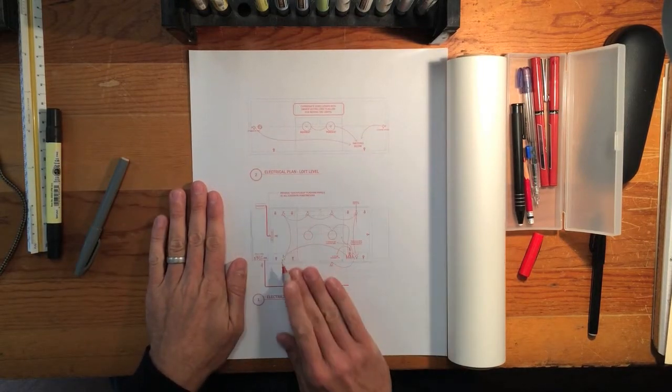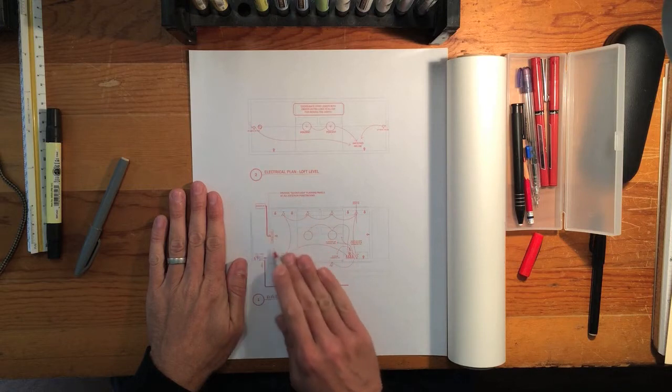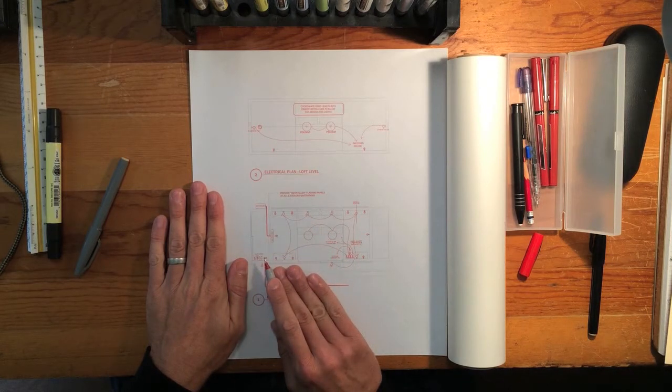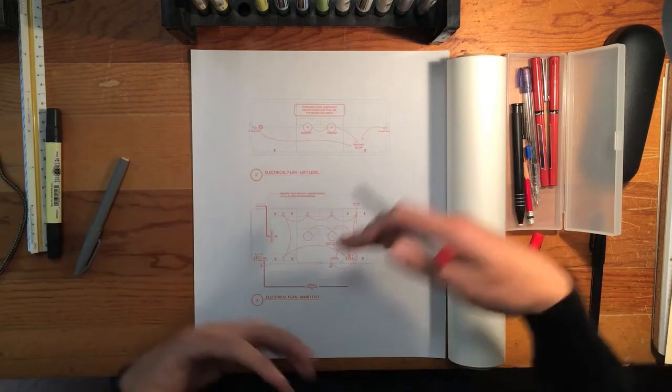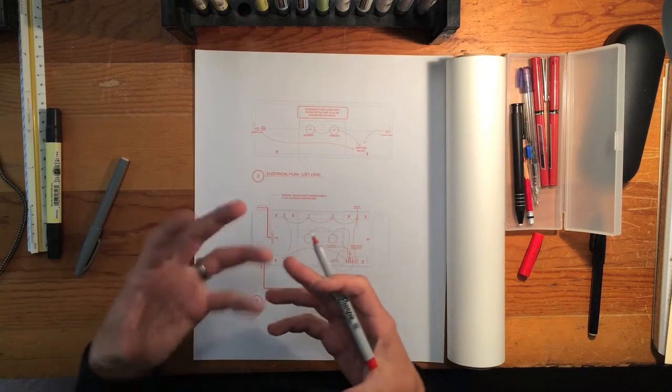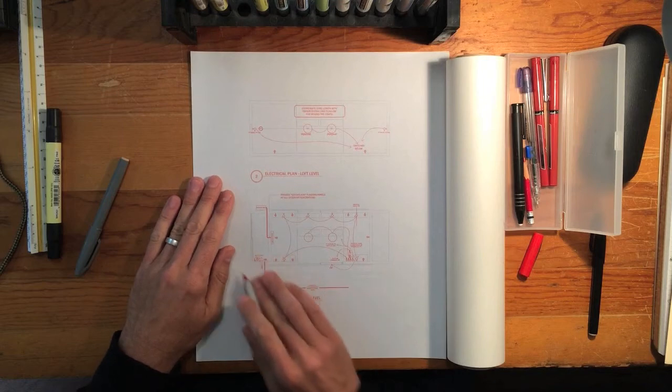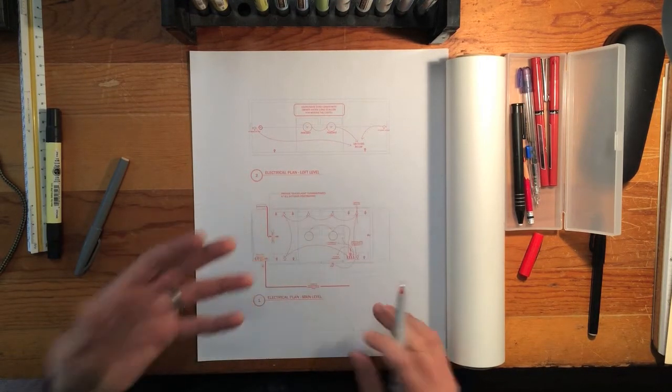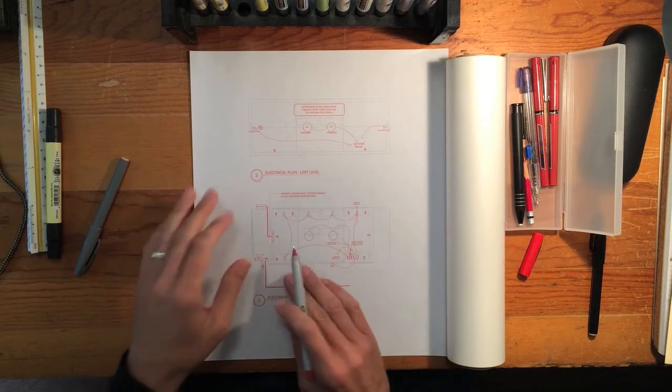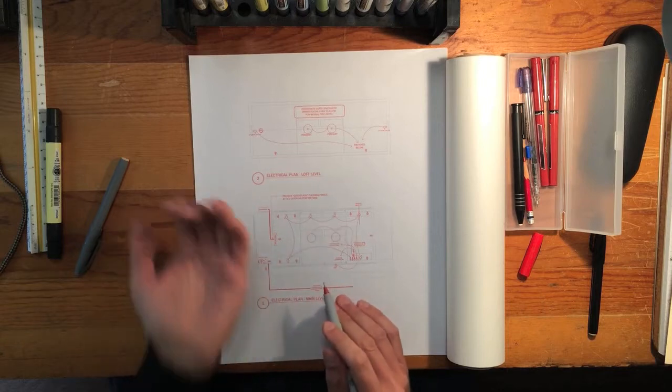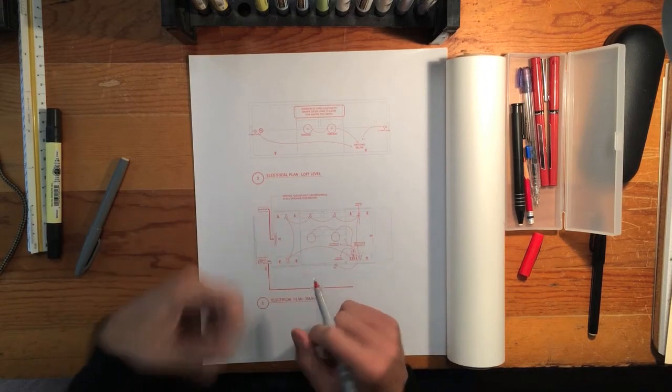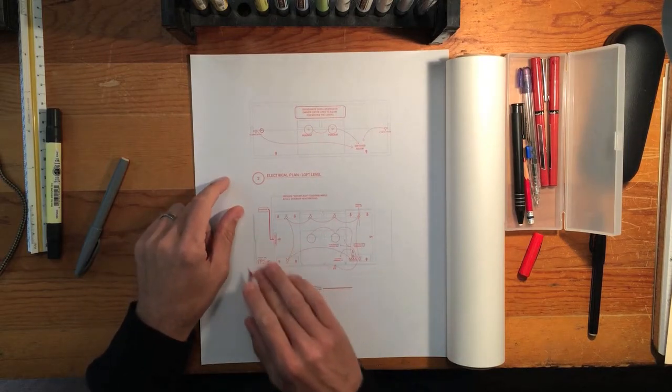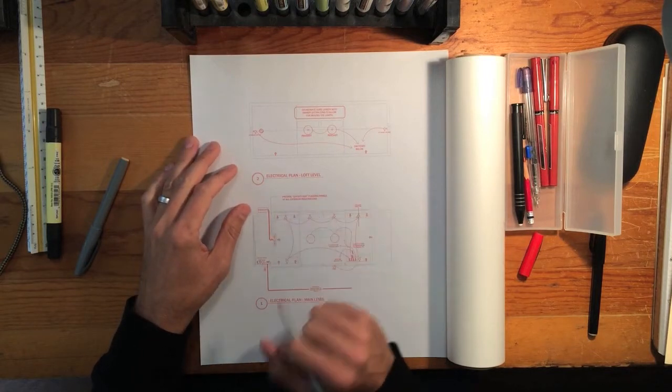A couple other things to layer onto this plan: obviously we need to be thinking about how the HVAC unit comes and gets power, so that gets shown on the electrical plan as well. You want to think about how all of these components impact the exterior shell of the building, and so I've specified some flashing components so that the details are all called out and nothing is left to chance. Last thing that we want to talk about is how power actually gets to the structure. This is a slab on grade, so it means you have to plan carefully for how power comes to the structure and comes up through the slab. You need to set your conduit before you pour your floor slab, and the floor slab is going to be one of the first things that's done, so this electrical plan needs to happen at a fairly early stage if you're doing a slab on grade.